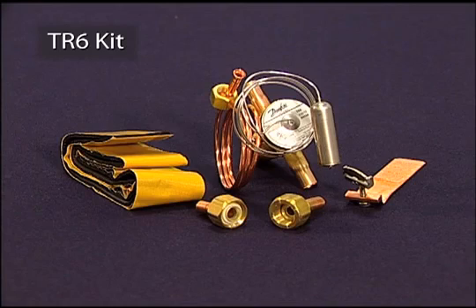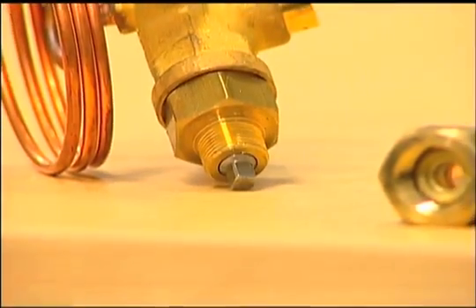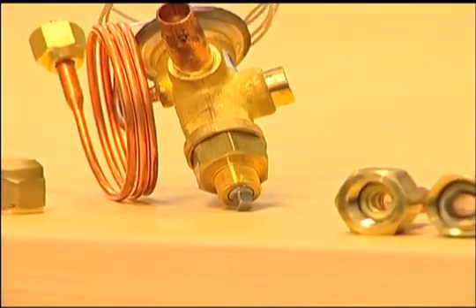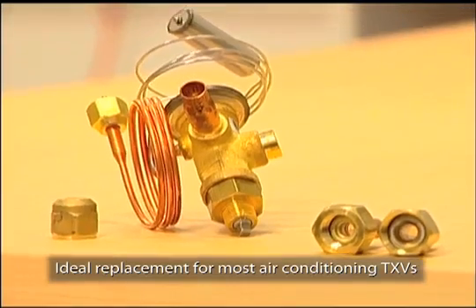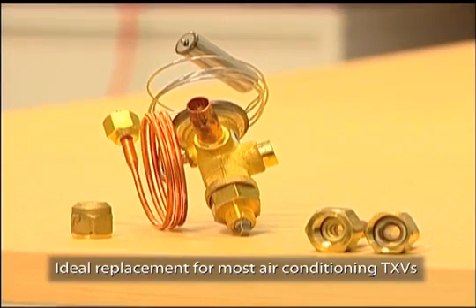The TR6 kit comes with everything needed for installation including a valve, bulb strap, insulating tape, and the two most common types of evaporator fittings: Aeroquip and Chatleff. With these two fittings and the valve's 3/8-inch ODF connections, the TR6 is an ideal replacement for most air conditioning thermostatic expansion valves. The aftermarket version also has a superheat spindle that can be adjusted when necessary to meet a system's needs.